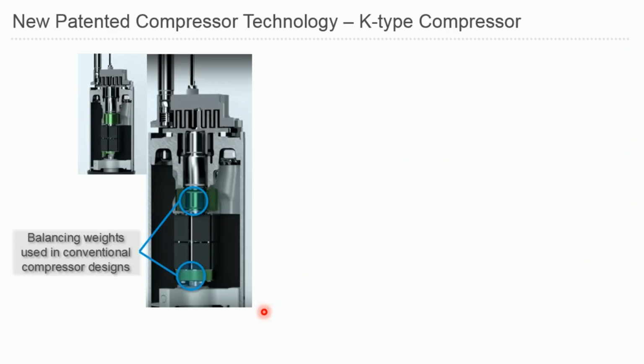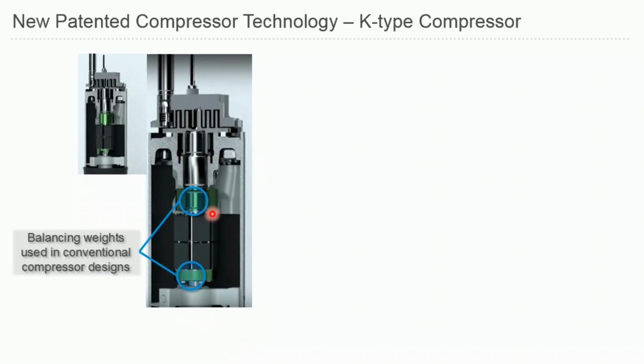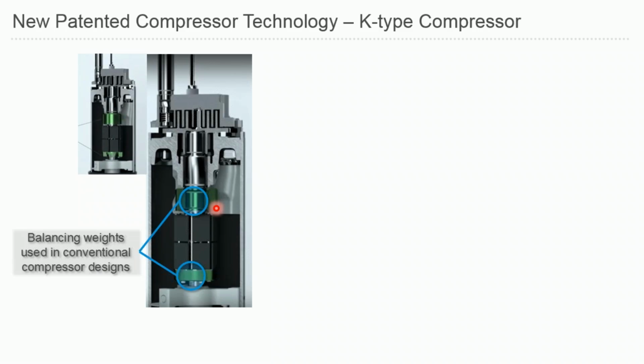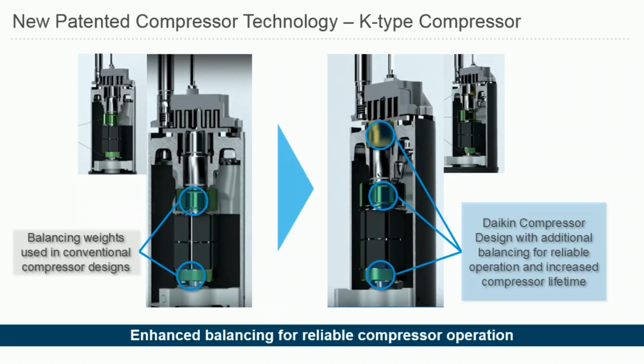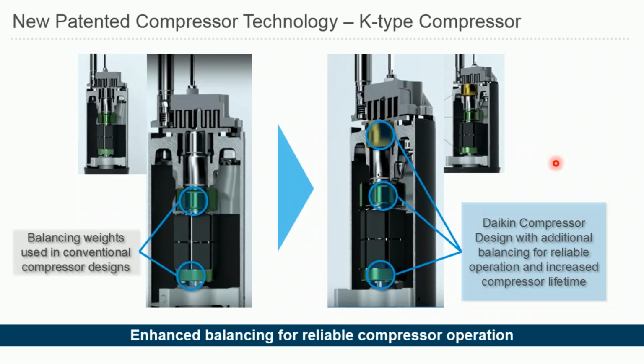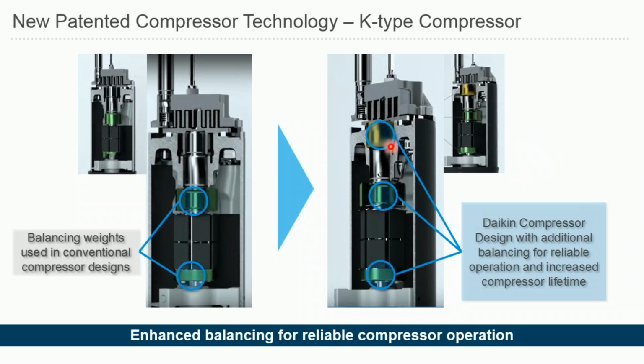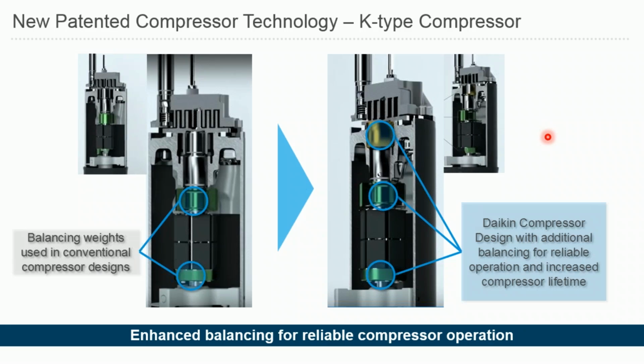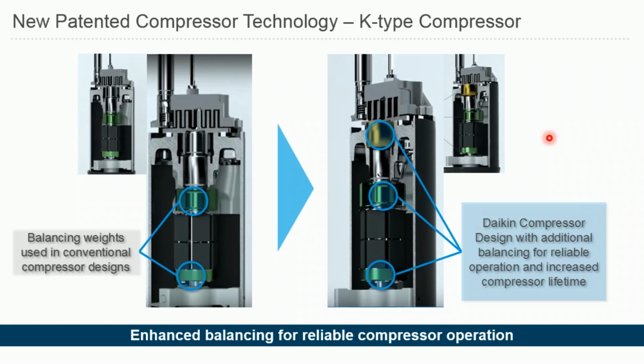Another improvement on the compressor design: normally with the existing scroll compressor design that we have in VRV4, you have two balancing weights that keep the operation at a stable level without causing any problems when more vibration starts happening on your compressor side. When you start bringing vapor injection into the equation, you start to see higher vibration levels on your system. To avoid that, we changed the design of the compressor and added one more balancing weight to keep the unit running smoothly without excessive vibration, especially when more vapor injection is happening throughout the operation. That's another thing that makes our compressor different from others.